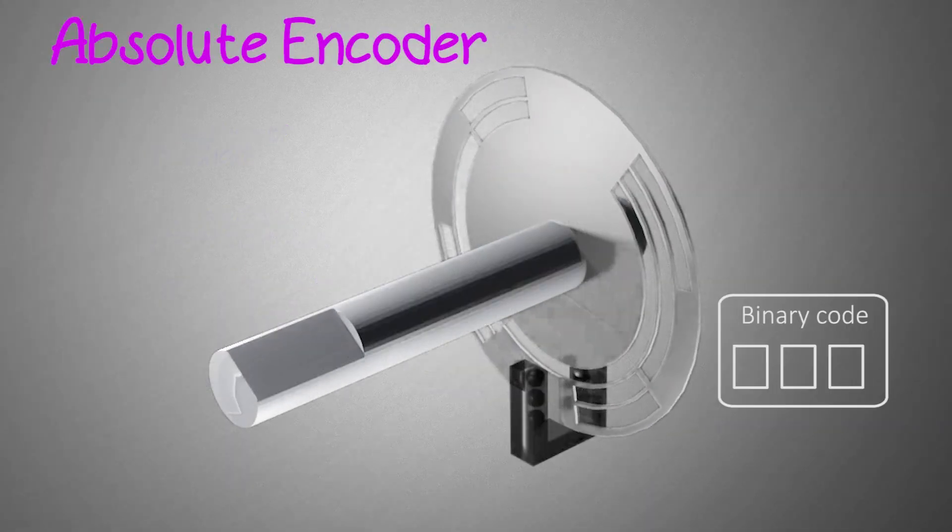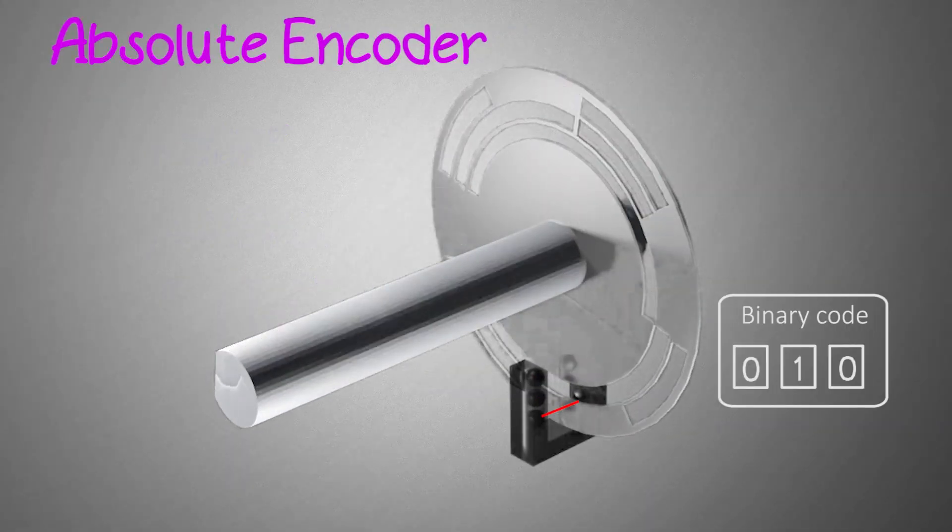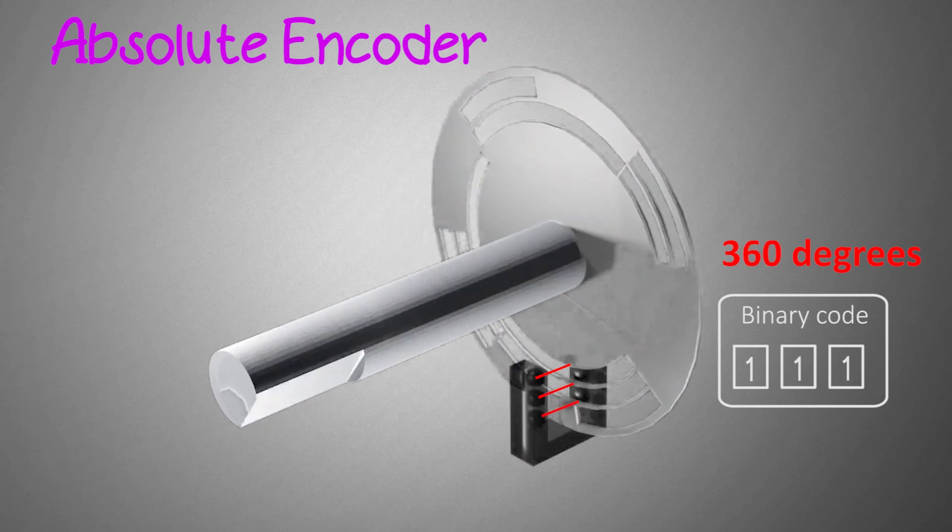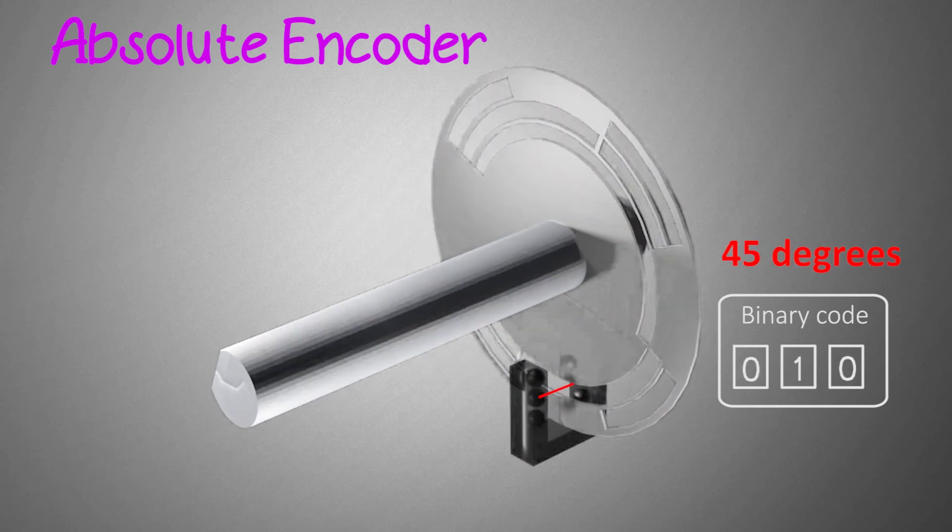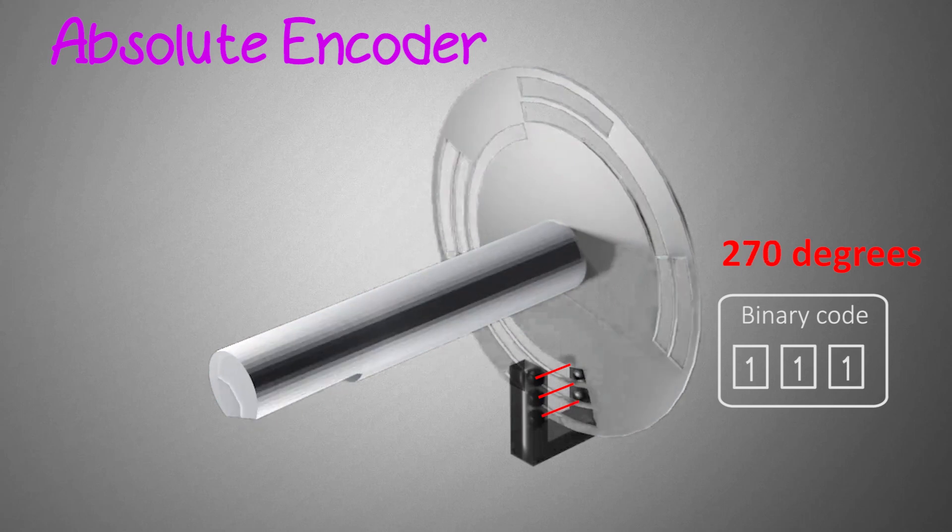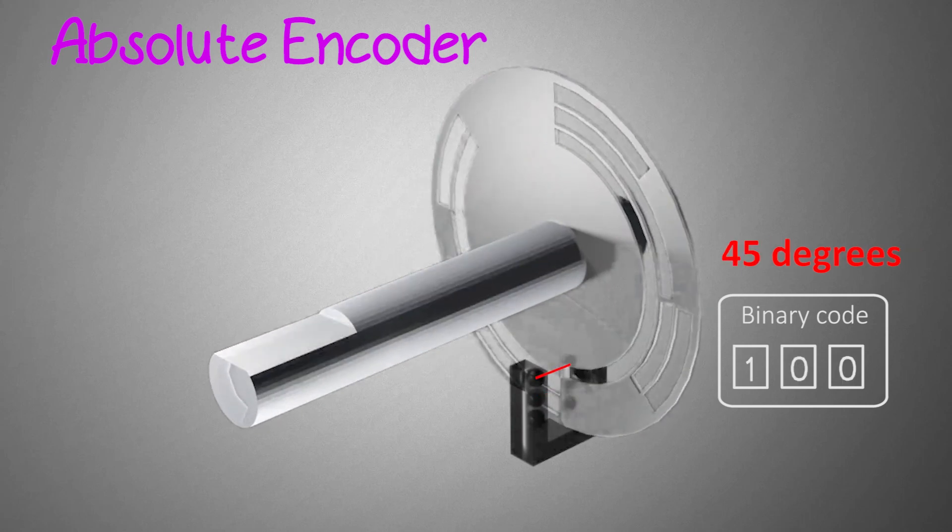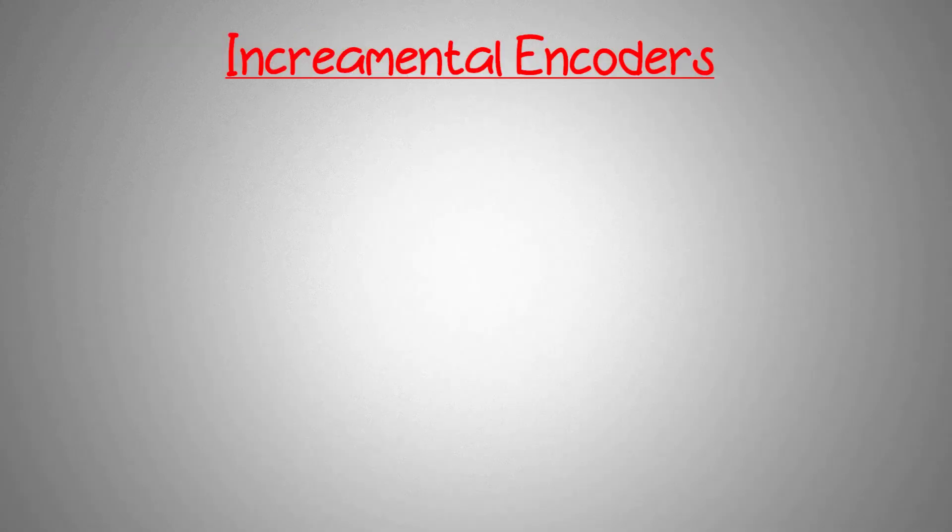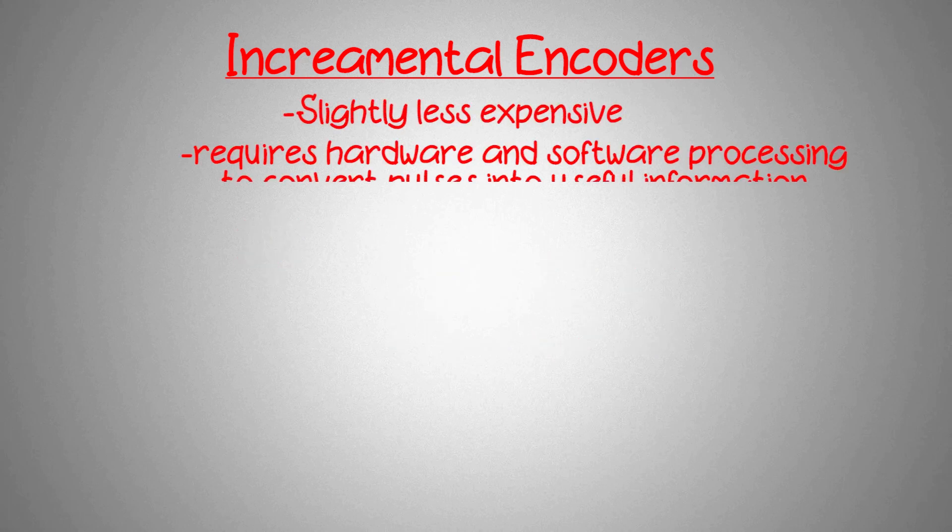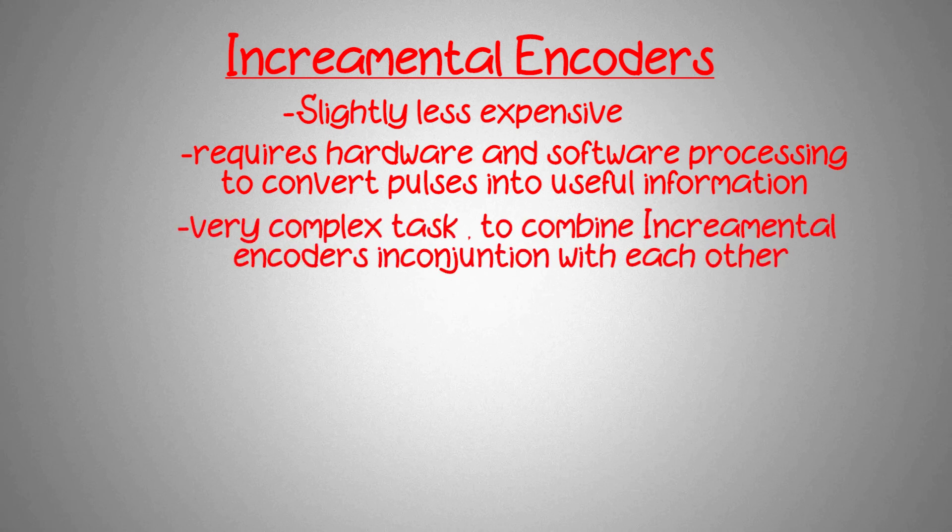The difference though is that the positions of the absolute encoders are each unique, and with a simple calculation you can convert the binary position value to an actual angle in degrees. Incremental encoders are slightly less expensive and also require the hardware and software processing to convert the pulses into some useful information. This adds more complexity as we combine the encoders in conjunction with each other. It's much easier to combine absolute encoders into the system.